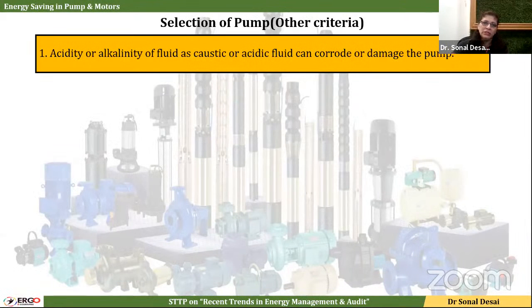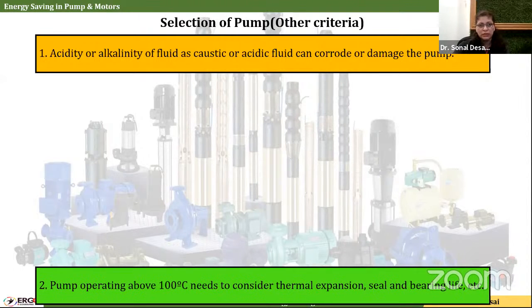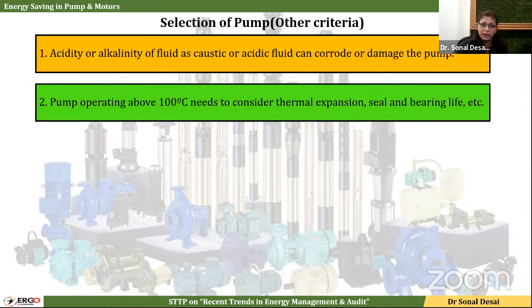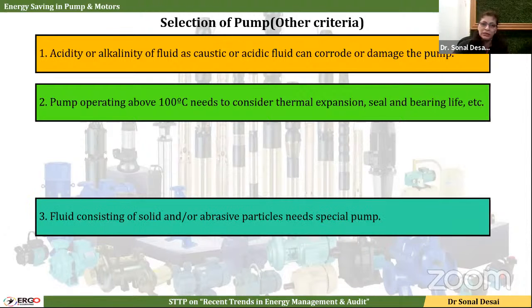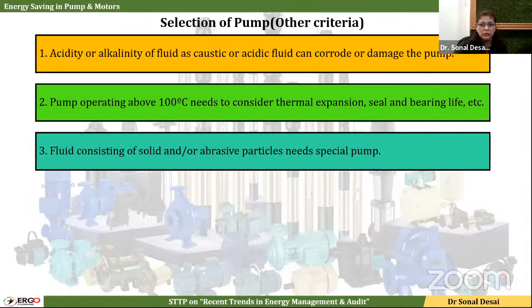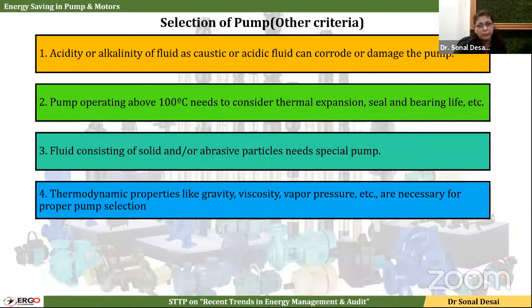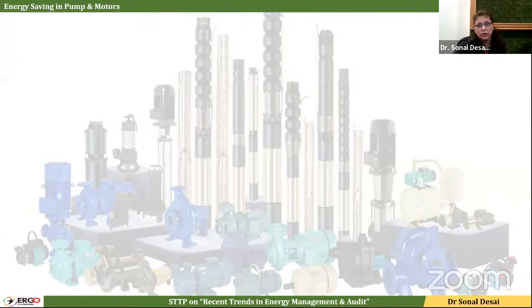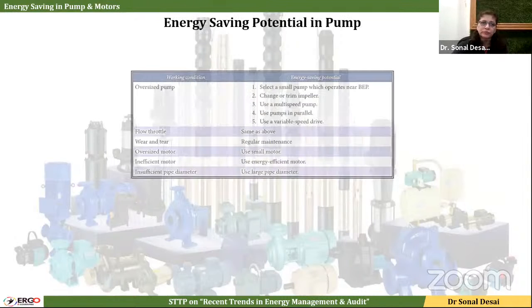Other important parameters deciding pump selection are whether the fluid handled is acidic or basic in nature. If the pump is operating above 100 degrees centigrade, then we should consider the expansion of the bearing, seals and other parts. If the fluid has abrasive particles, then again we have to select the impeller and internal construction accordingly. What are the thermodynamic properties of the fluid? If a fluid other than water is used, what quality is there that we have to consider.